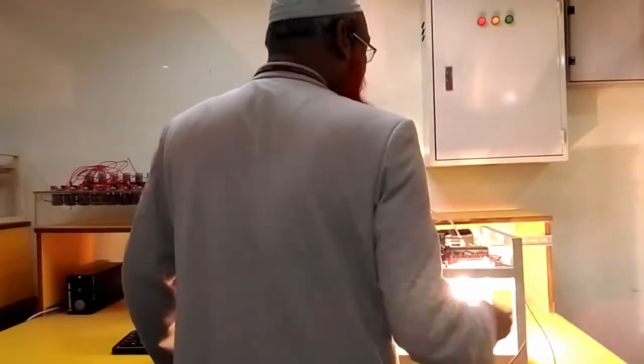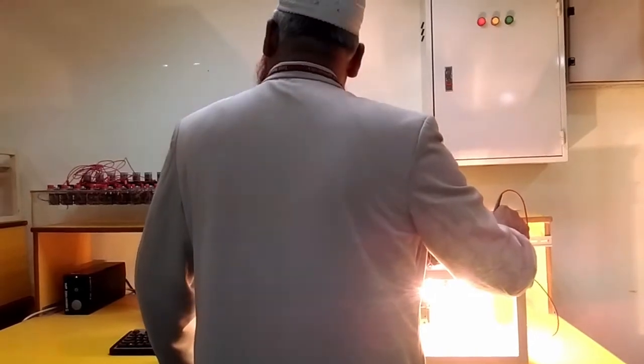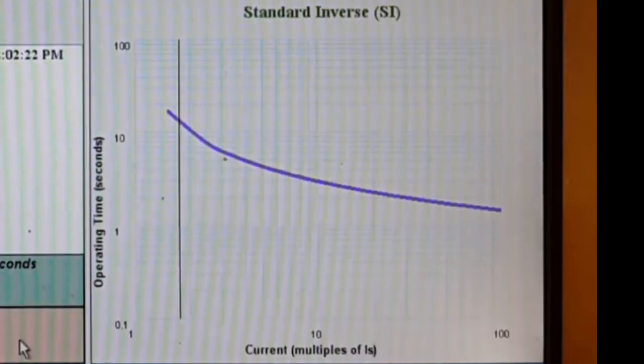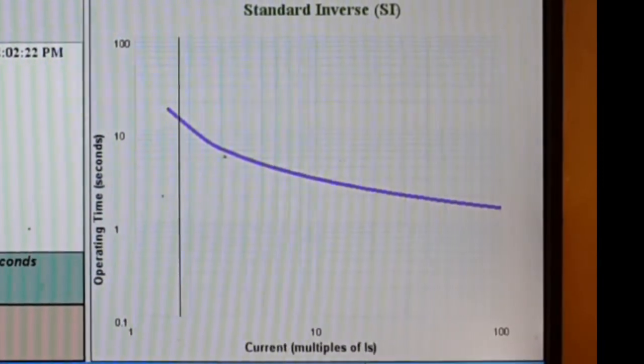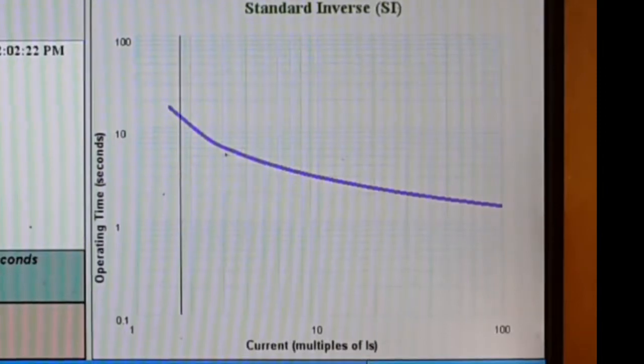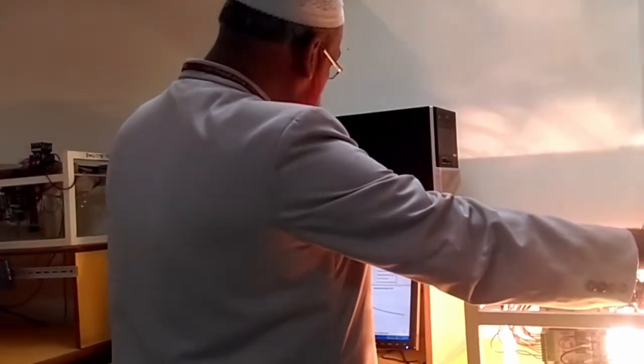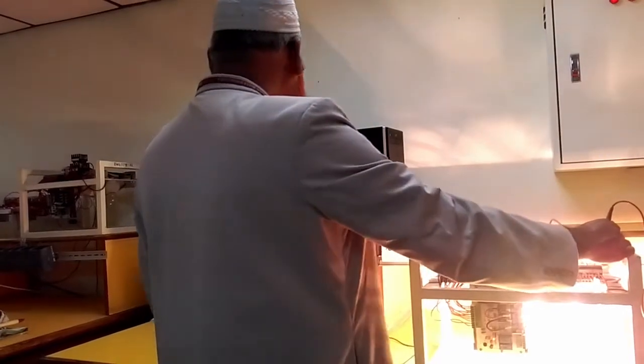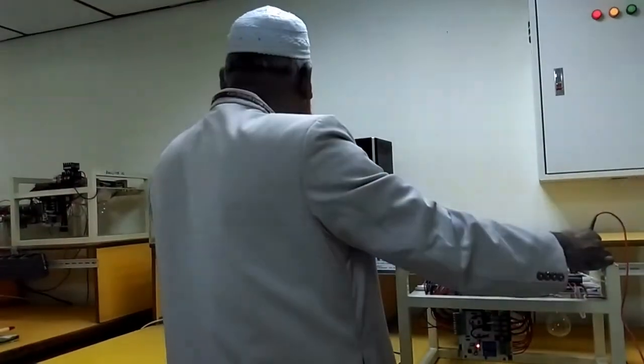We are now creating a fault. You can see that on the characteristic curve, a line is appearing. Graphically, you can see the operating time — it is about 12.95 seconds. This makes it easy for students to understand the behavior of the numerical relay.